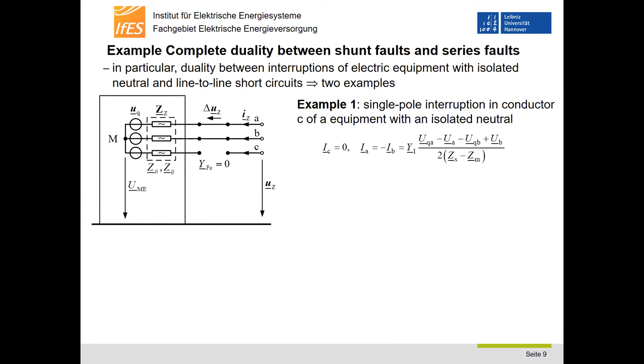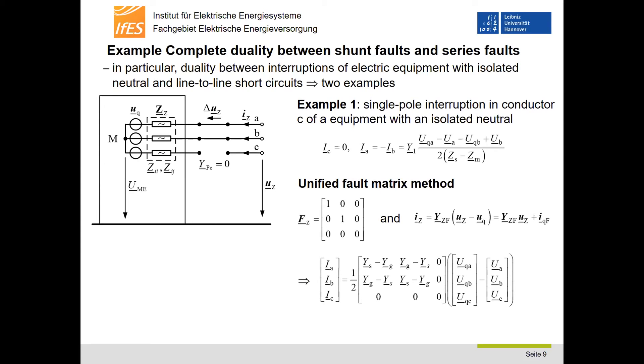The single-pole interruption in conductor C of an equipment with isolated neutral is shown in the figure on the left-hand side. The current in conductor C is zero. Due to the isolated neutral, the currents in conductors A and B are opposite and equal. They can be calculated using a mesh between the branches of conductor A and B. The currents depend on the two voltage sources of conductors A and B and the double positive sequence impedance. The same result can be derived directly by applying the unified fault matrix method to the branch equation system. The current IC is zero according to the fault condition, setting the neutral admittance to zero is easily possible, and the three-phase structure is maintained.